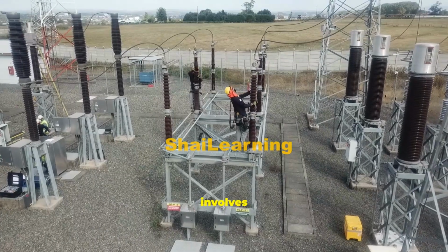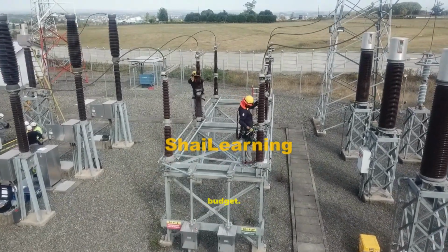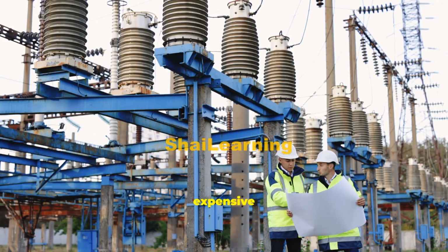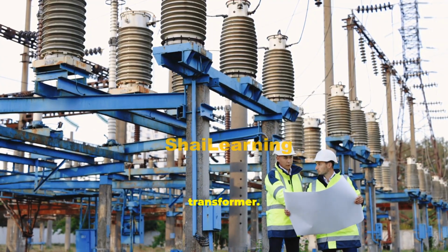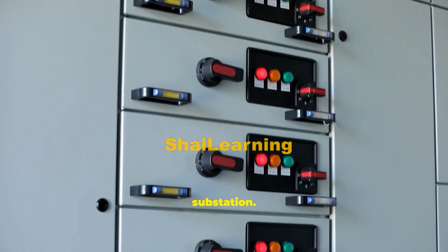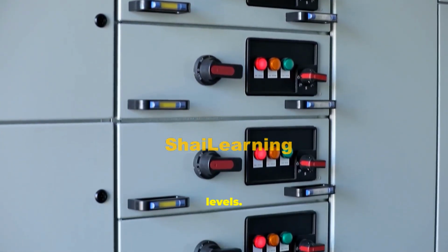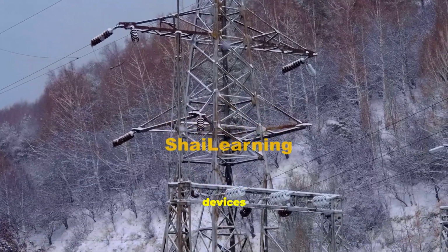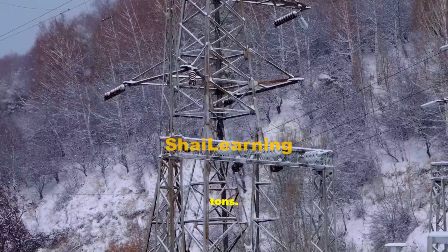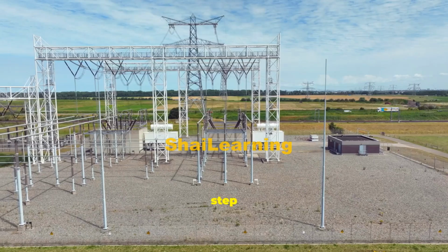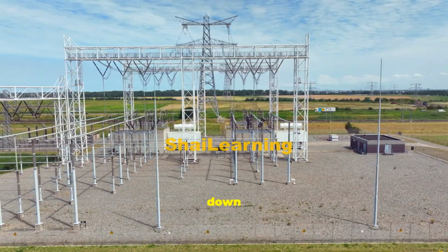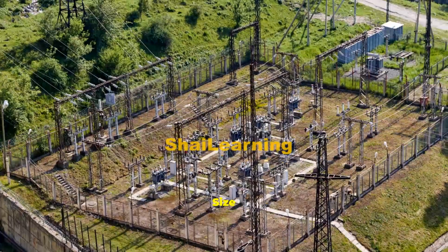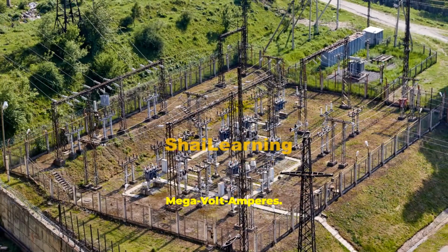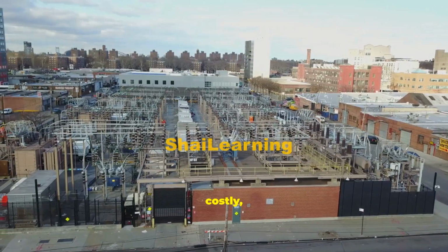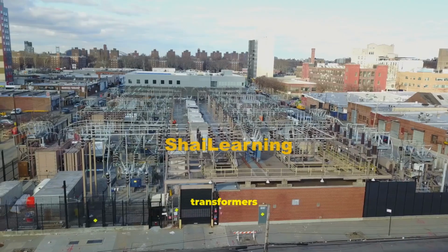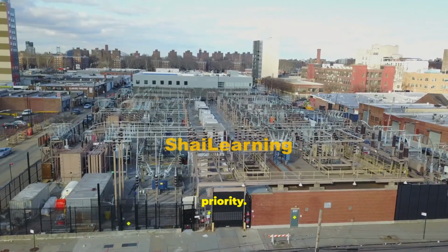Choosing the right layout involves careful trade-offs between reliability needs and budget. The most prominent and often most expensive piece of equipment is the power transformer. This is the heart of the substation. It changes voltage levels. Transformers are massive, oil-filled devices that can weigh hundreds of tons. They work on magnetic induction. They step voltage up for transmission or step it down for distribution. Size and capacity are rated in megavolt amperes. Because they are huge, costly, and have long lead times, protecting transformers is a top design priority.